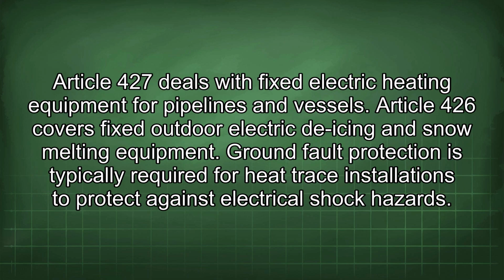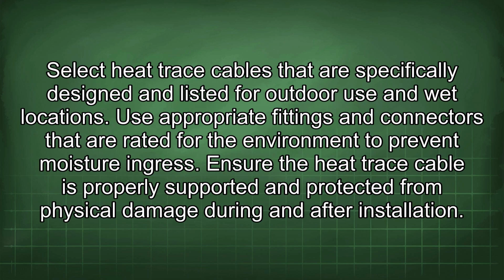Article 427 deals with fixed electric heating equipment for pipelines and vessels. Article 426 covers fixed outdoor electric de-icing and snow melting equipment. Ground fault protection is typically required for heat trace installations to protect against electrical shock hazards. Select heat trace cables that are specifically designed and listed for outdoor use and wet locations.